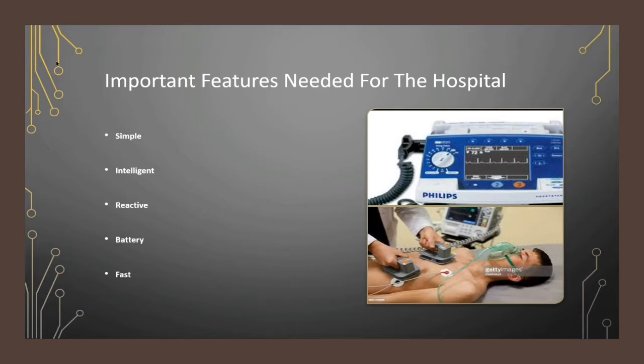High capacity and long life battery. The unit should be able to charge to maximum energy in a short time. The patient's heart rhythm is analyzed in seconds. The defibrillator's ECG input amplifiers should be protected against damage from defibrillator energy. The display should recover a readable ECG graph within 5 seconds of an input overload from a maximum energy defibrillator pulse.